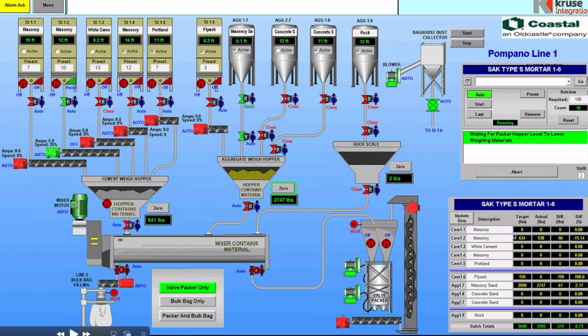So at 624, it will close, it will shut off. And that'll be even after the dribble mode. So once it goes into dribble mode, probably around 600 pounds, and then at 624 it stops because there's always material that falls in. And the preact is saying there's about 10 pounds of material that falls in after we tell it to stop.